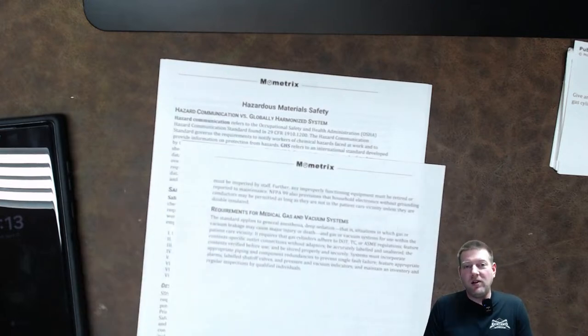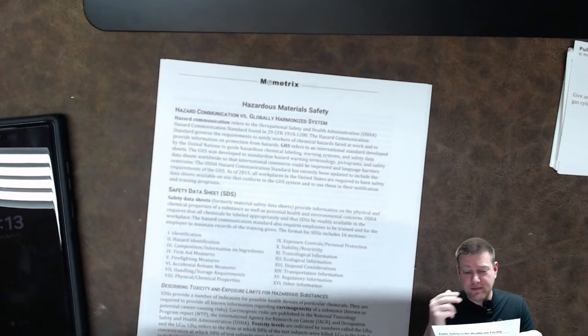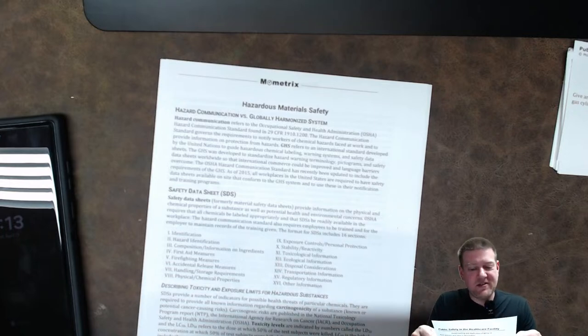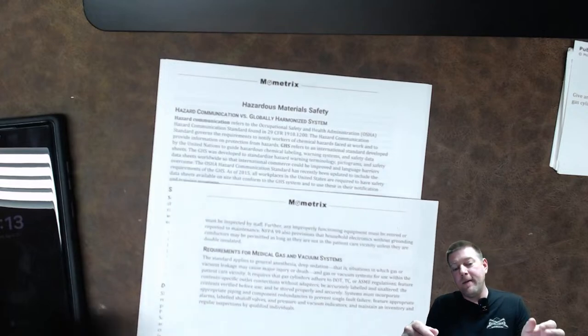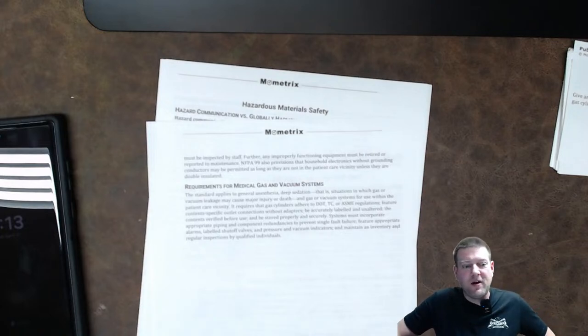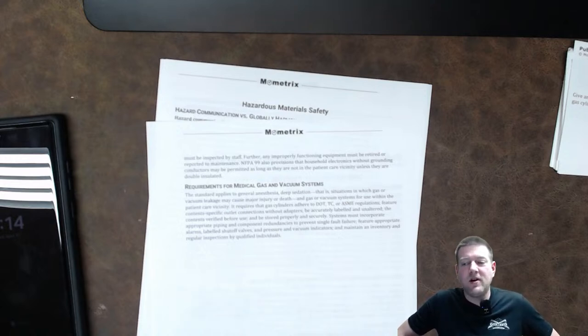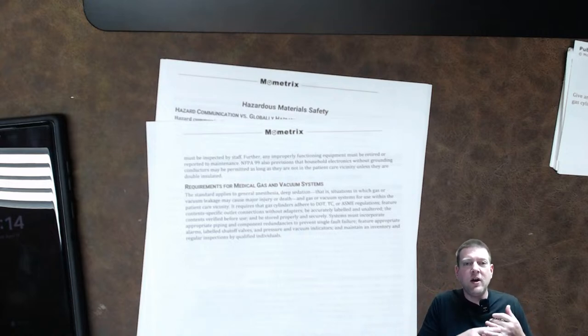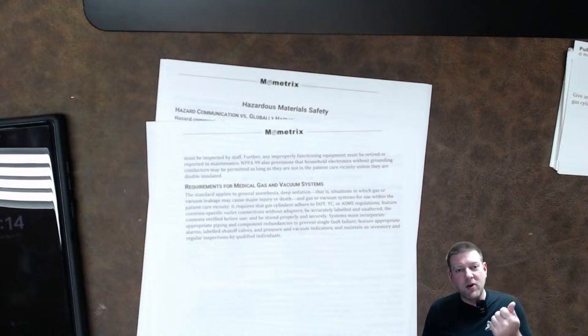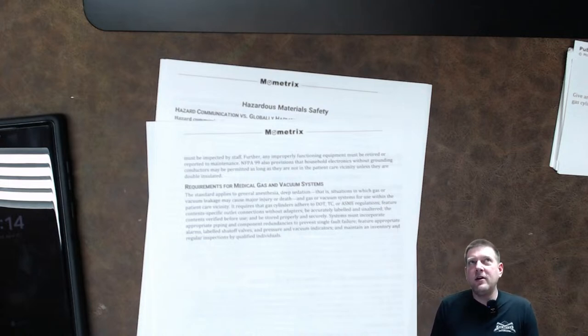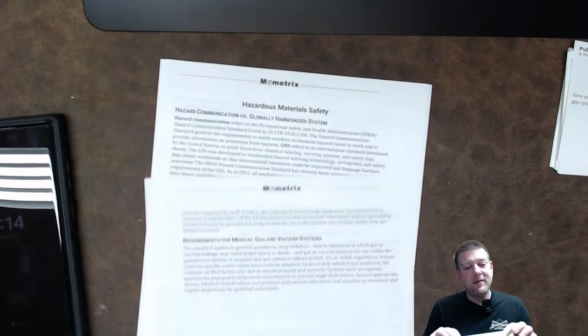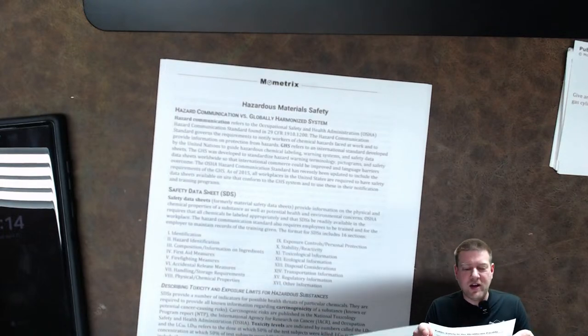NFPA 99 also provisions that household electronics without grounding may be permitted as long as they're not in the patient care vicinity unless they're double insulated. Well, a lot of radios and stuff out there are not double insulated, and you'll find those in patient care areas. Every hospital has different policies. When it comes down to inspections, notice it didn't really say anything about whose responsibility it is to inspect. In many facilities that I've been in, if a patient care item comes in and the patient owns it, then it's up to nursing staff to check it out and make sure it's safe, which means no defects in the cord, no obvious abrasions, and make sure that the prongs are secure and they're not broken off, and then it can be used in a patient care environment. Remember, if you touch it, you own it. So, minimally invasive is what we're talking about for most inspections. Because if you break it, well, then now you've got to buy them a replacement.